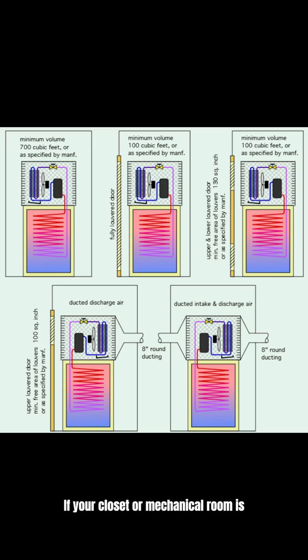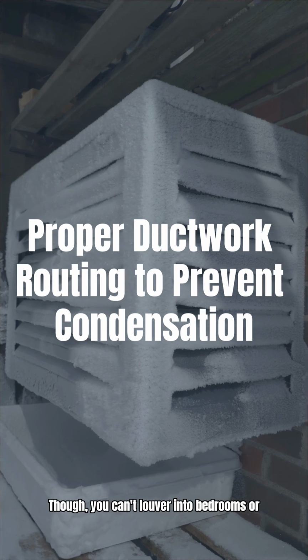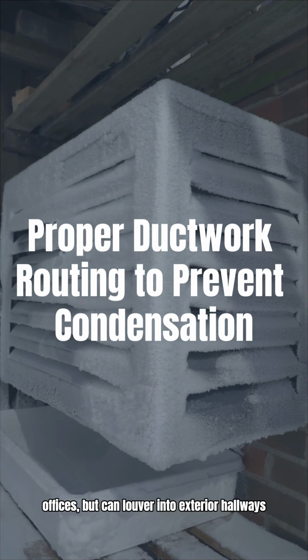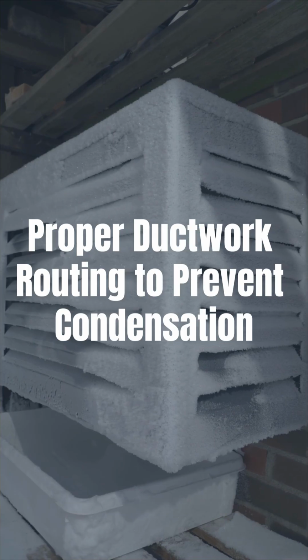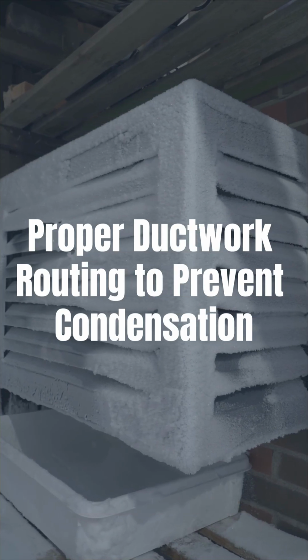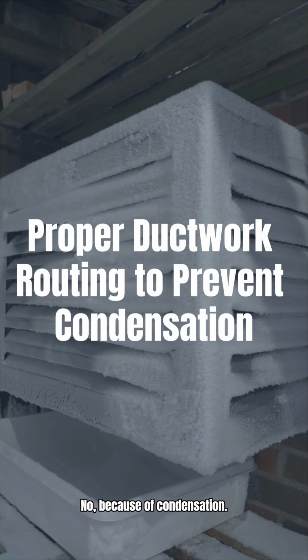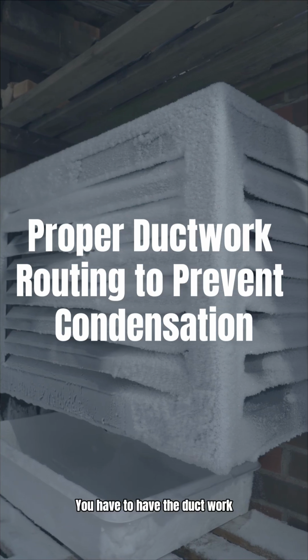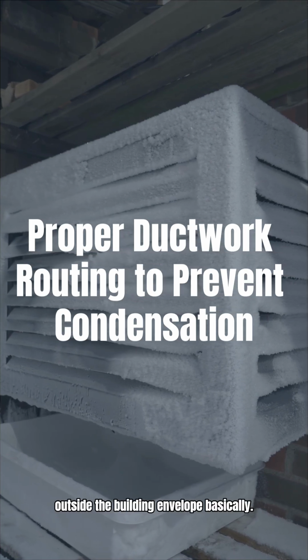If your closet or mechanical room is too small, you might need louvers or to move the whole thing to ensure enough airflow for the heat pump water heater. Though, you can't louver into bedrooms or offices, but can louver into exterior hallways or rooms with heat loads instead. Can we duct it to the attic? No, because of condensation. You have to have the ductwork outside the building envelope basically.